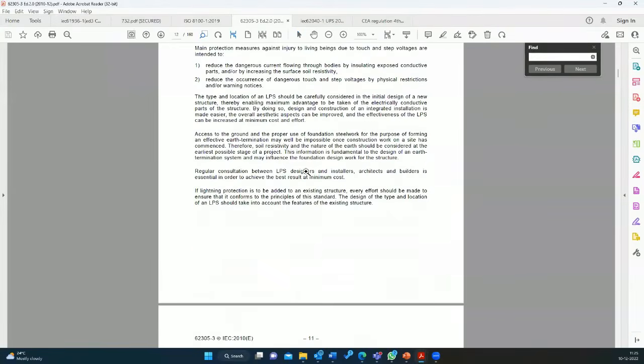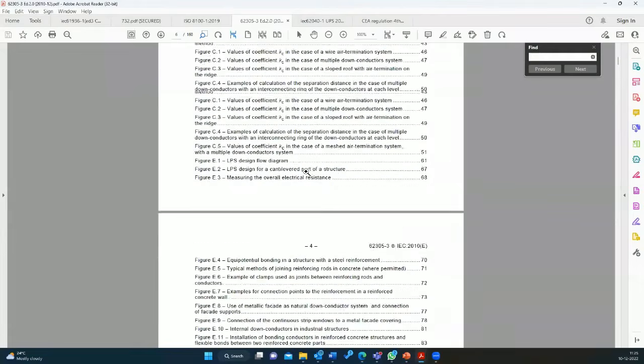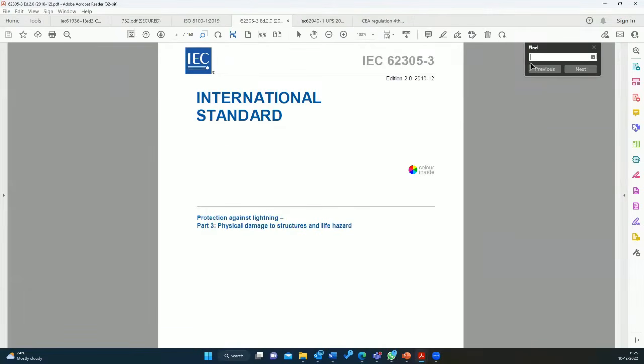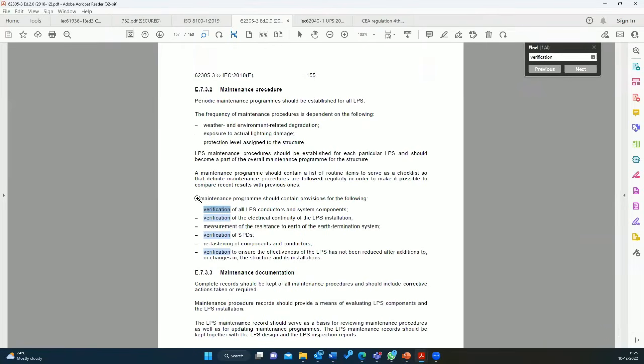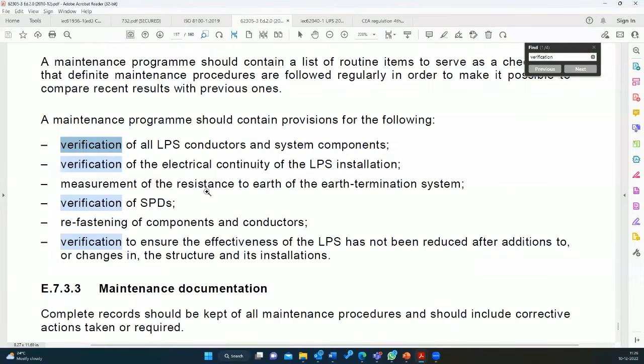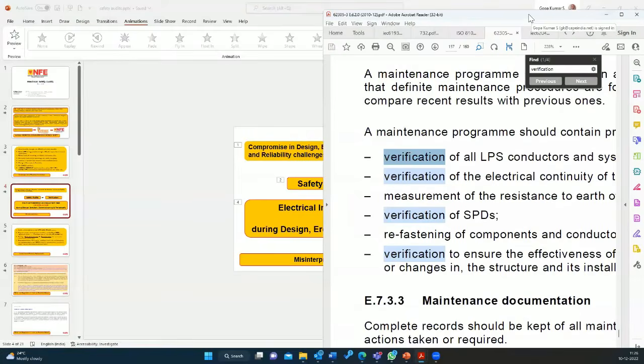Next standard, the lightning protection standard IEC 62305 Part 3. I'm sure all of you know about this standard as well. Here, let us search for audit. Of course, no audit, then the word verification. So verification is used in 4 places in this particular standard. A maintenance program should contain provision for the following: verification of LPS conductors and system components, verification. So always the word which is used is verification. It is not audit. So when we read it, we have to be very careful in understanding this.